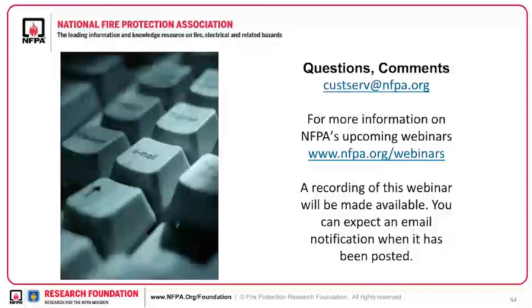Let's see, next question I'm seeing is the UL 9540A test methods provides gas composition, heat flux, and other data needed by fire protection engineers and AHJs. Does the FM method provide this data? So first of all, FM Global does not have a sort of publicly available test protocol. We have these tests that we've conducted, which in fact align fairly well with what UL 9548 does. One of the bigger differences is that 9540A looks for an implicit result. So you're testing one system and you're determining protection guidance or separation distance or something for that one system. And so that can be a very specific result for that system.